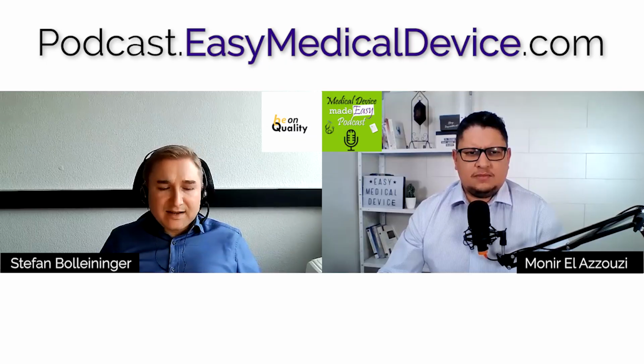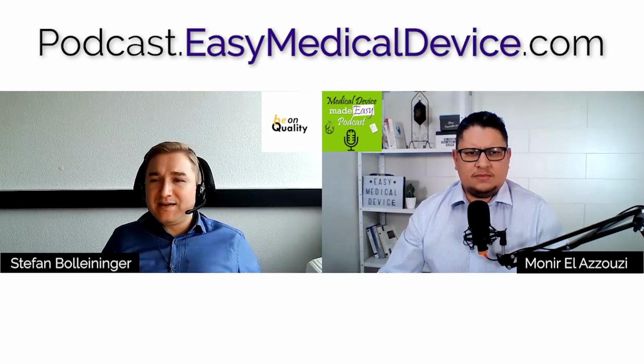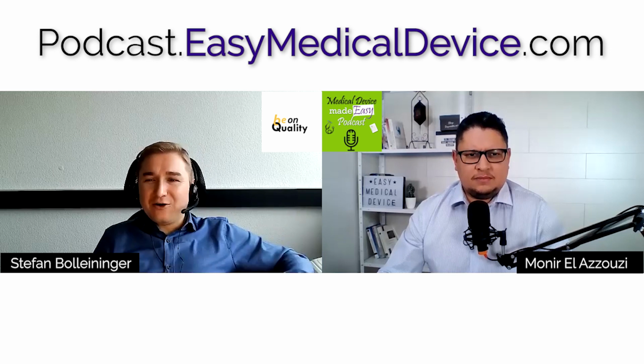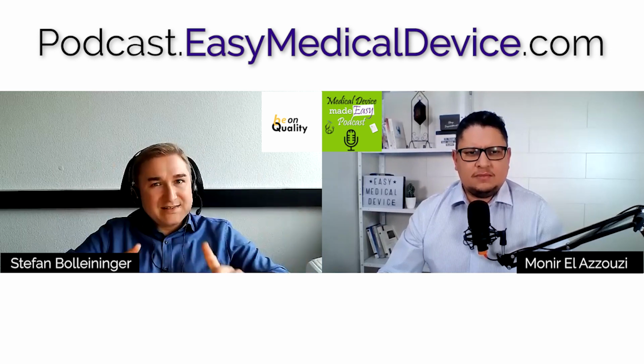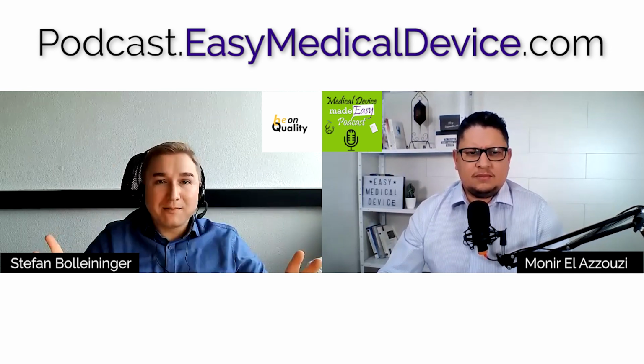But always please do not forget, because you cannot do a clinical evaluation, because you don't have a real clinical use, don't forget to do a performance evaluation. That's something which some people forget because they look into it and say, okay, clinical is not needed. We are not a medical device, so they strike it out from the list. But performance evaluation is always possible.